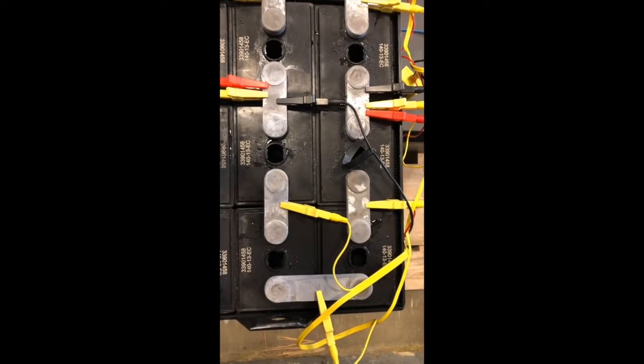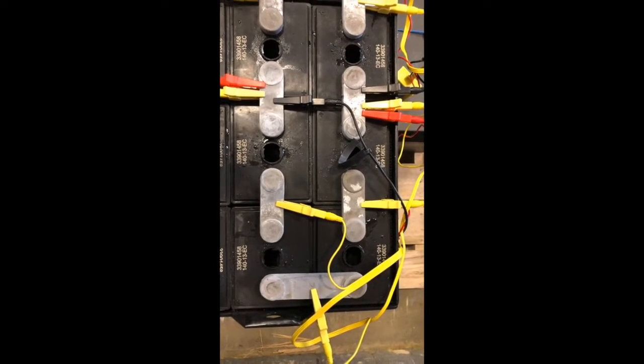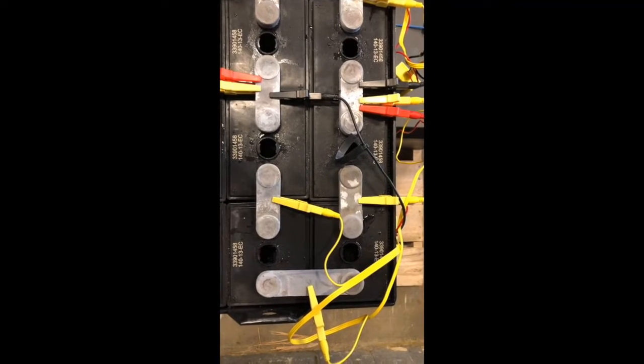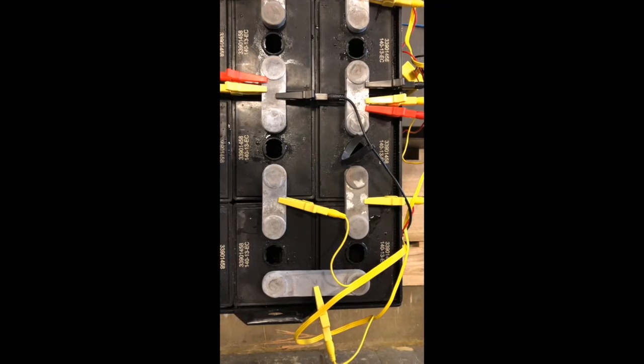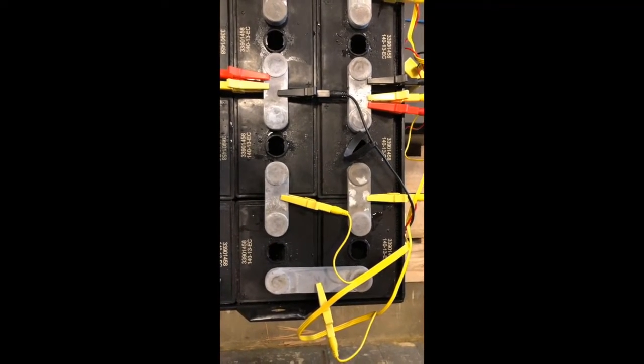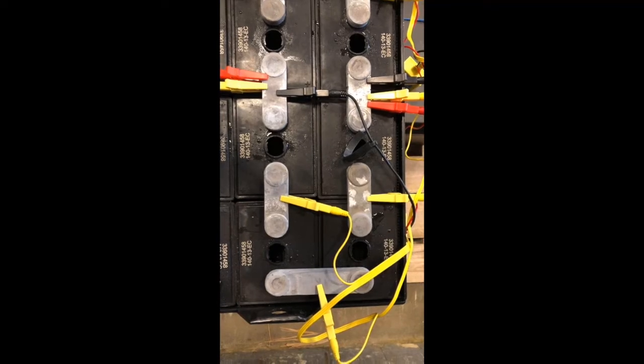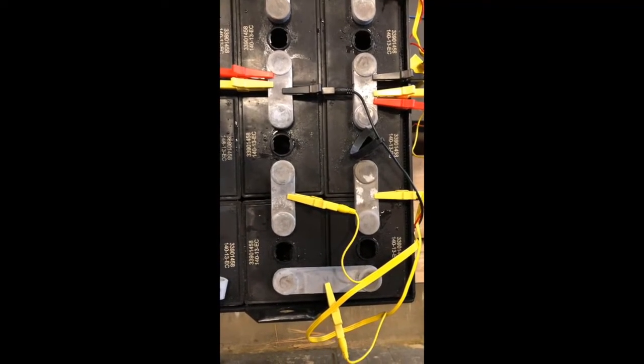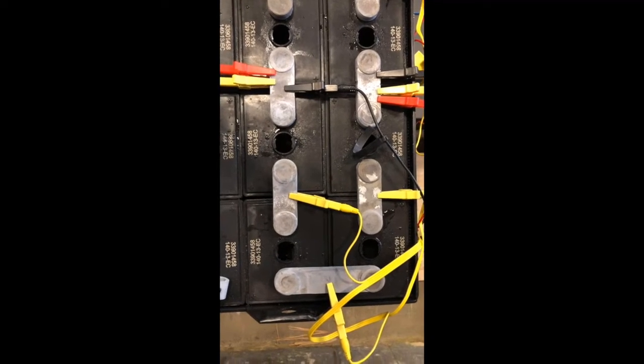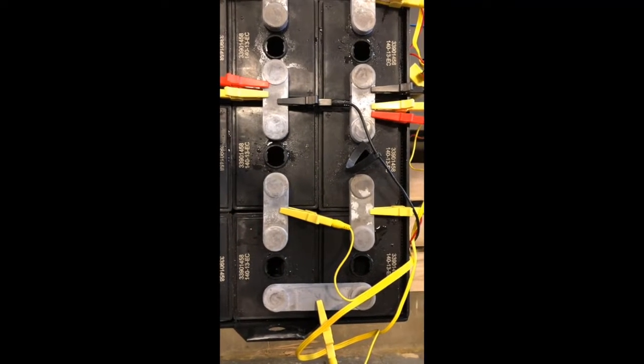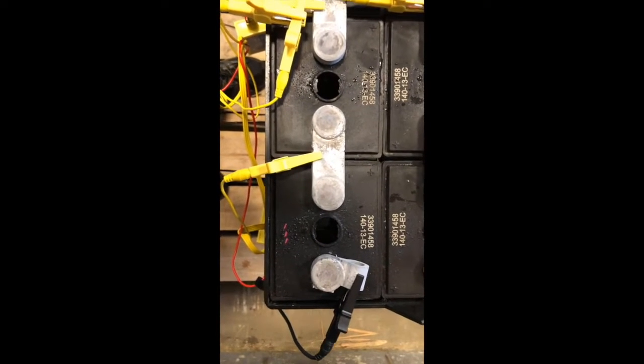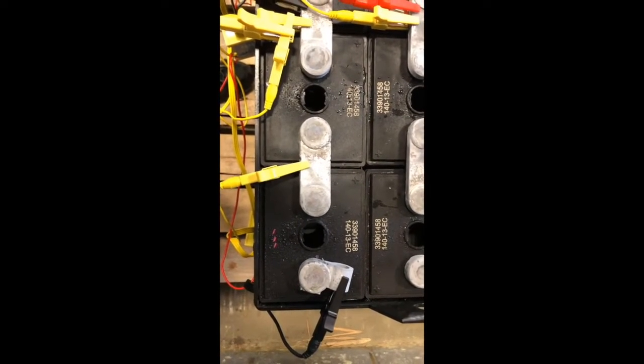When connecting the second module on 2-volt cells, the longest yellow and the red land on the same intercell connector or electrical point as the black from the previous module. Again, the order is longest yellow goes with the red, next longest yellow goes on number 6 positive, the second shortest yellow goes on number 7 positive, the shortest yellow cable goes on number 8 positive, and the black goes on number 8 negative.